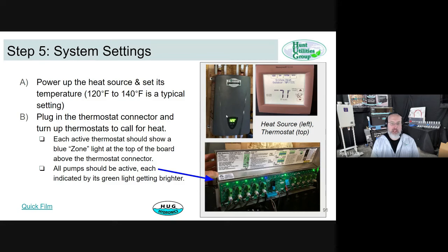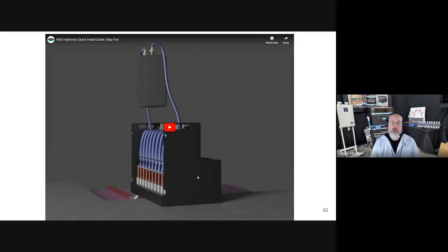Just keep in mind that the temperature coming out of the boiler isn't directly the temperature going into the floor. If you're adding enough BTUs to overcome the heat losses, things will warm up slowly, or will keep warming up, and then once it satisfies your thermostats, things will be good. We're going to plug in the thermostat connector and then turn up each thermostat to call for heat. You'll see a blue light come on.